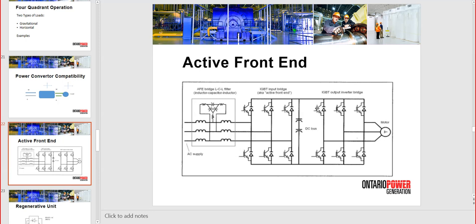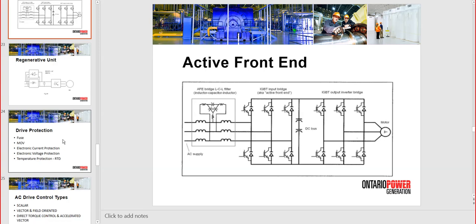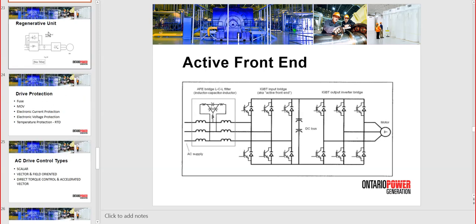Active front end solved the problem with the VFD. So now, instead of using diodes, if you say I need an active front end drive, then your drive will have the same configuration but a different control type. The control on the rectifier will be as such. The capacitor banks are always fully charged, and you will need to have an input filter, because the input filter is the one that protects others from the power you're gonna generate back to the grid, right? So whenever the motor becomes a generator, it will inject power to the DC, and the DC synchronized to the grid will inject that power back to the grid. Any questions regarding active front end?